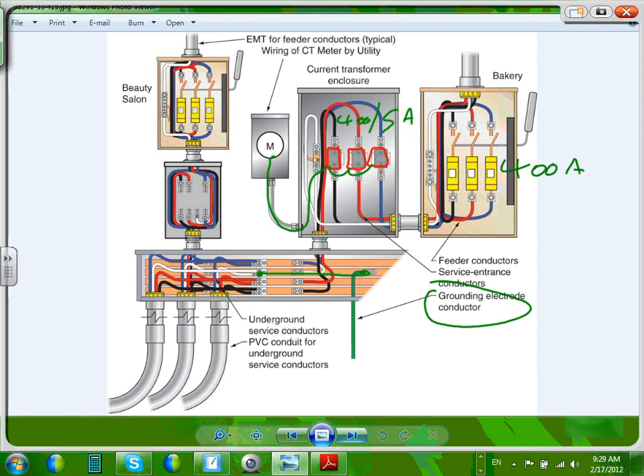This one, this, protective device for the... Oh, what is it? Give me 1 second here. Let me just see what's the other one. What was that one? This is a 200 amp. This one is 200 amp. Okay. For up to 200 amp, the electronics can take the amps and sense them directly, the meter. If you go higher than 200 amp, if you put more than 200 amp through the jaws of a meter, you'll burn it. So the smarter people said, okay, I'm going to put a CT.